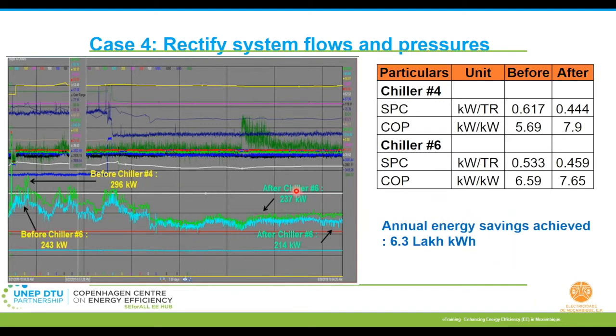If you look at the graph here, this is a control system graph from the monitoring system in place. This is system monitored information, not plotted by us. There were 2 chillers, chiller number 4 and chiller number 6. They were initially consuming about 296 kilowatt and 243 kilowatt. After intervening with different measures to improve the operational efficiency of the entire system, the power consumption has come down to 237 kilowatt and 214 kilowatt.